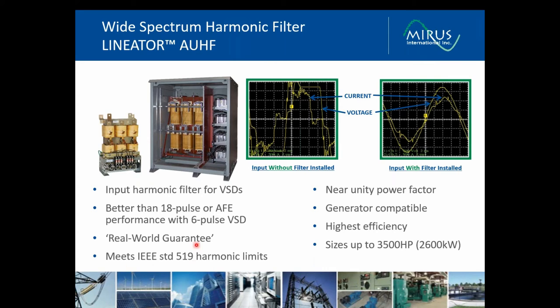We have a real-world guarantee. If there's background voltage distortion and voltage imbalance, it will still meet our performance limits. We restore the power factor to near unity. We're compatible with generators by ensuring that the capacitive reactance of our filters is quite low and within the reactive power capability curves of the generators. Very high efficiency. We'll talk to that a little bit. So you're saving on energy and emissions associated with the operations of the generators. And we can do large sizes. At this point, 2.6 megawatts is the largest, but we definitely have designs for larger systems and well over 10,000 filters in service to date.